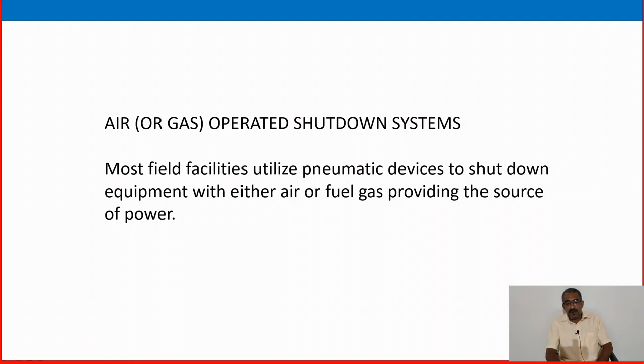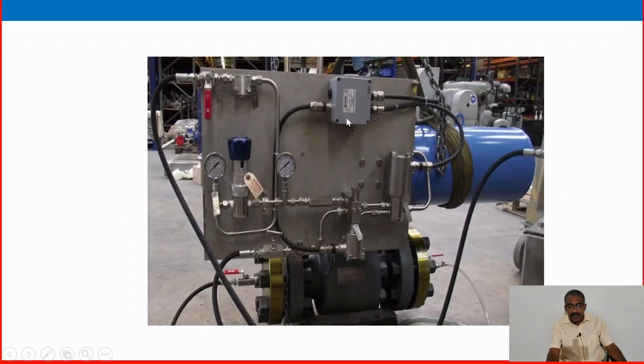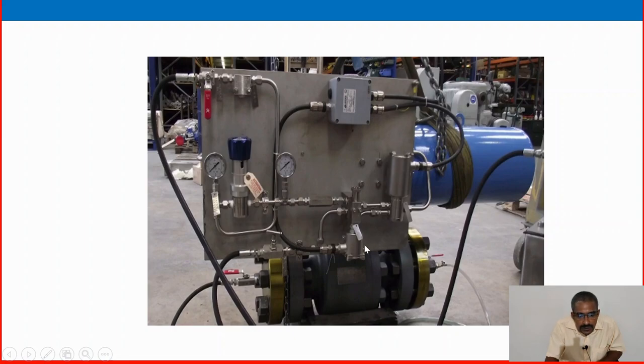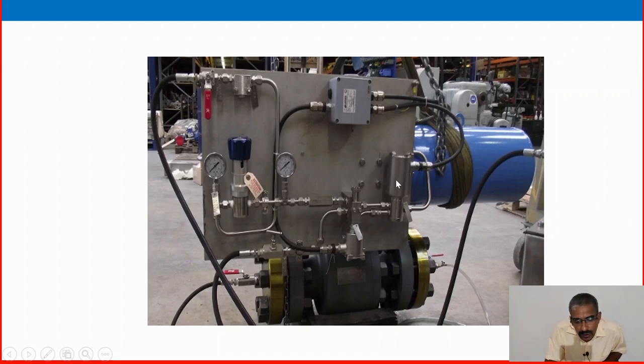We already discussed that — the air system is coming here. This looks like a solenoid valve. You have to check where it is in this picture. This is the air coming in, the air regulator is here. The compressor air comes in, goes into the regulator to regulate the pressure. This one is a pneumatic solenoid valve. Solenoid valve needs an electrical supply and pneumatic air — this is also required.